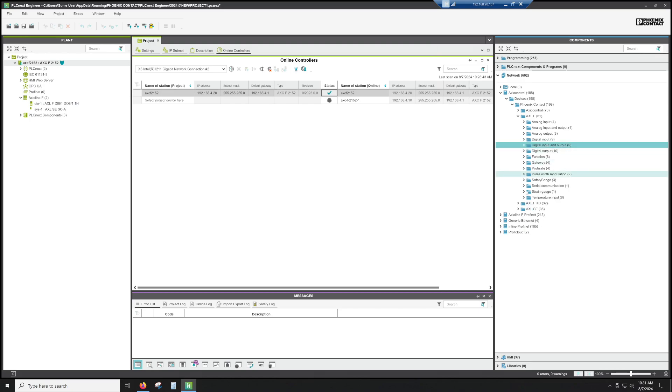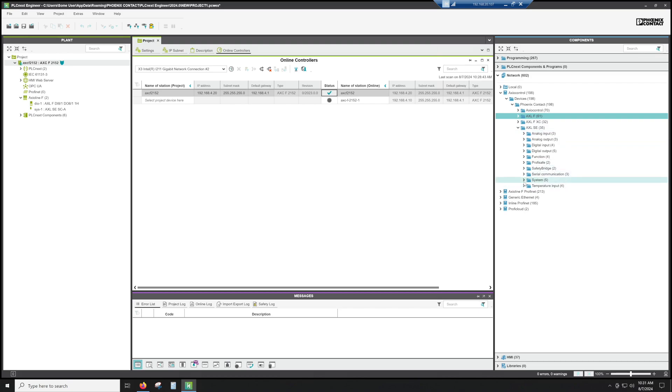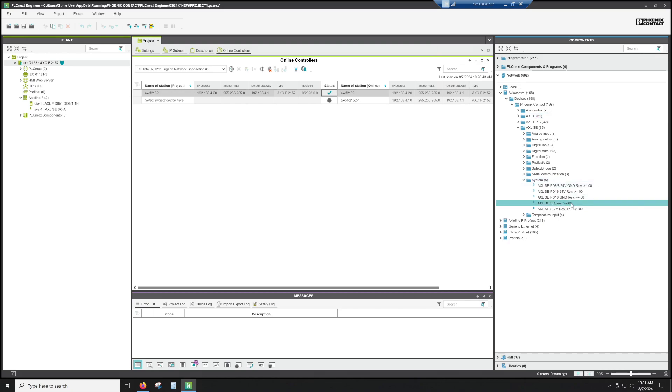For smart elements, you're going to get out of the AXLF and go to AXLSE. I don't have any modules currently in there except a slot cover. So that would be under system. And then there's an SC, which is an SC non-active. So that's basically a blank slot with no card in it. An SC-A was sort of the original card, and any blank slots needed an SC-A. That's been removed, and now there can be just blank slots.